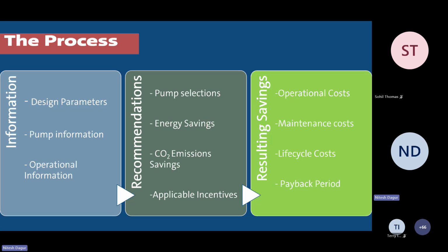So we collect this information from the site: the design parameters, like what the pump was actually designed for, the pump information, what pump it is, and operational information, such as if there's any automation, if there's a backup pump, or if there are multiple pumps, then which pump runs for how long, etc. Based on this, we make the recommendations to the customer.